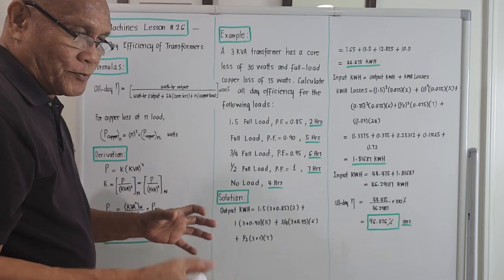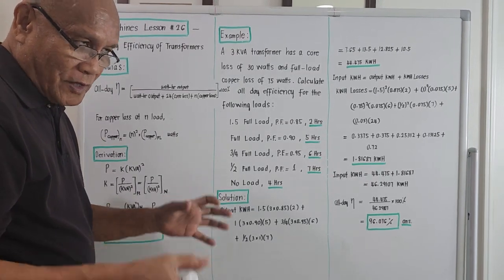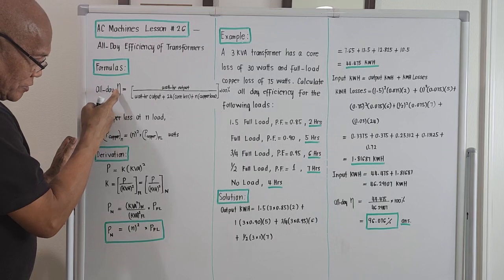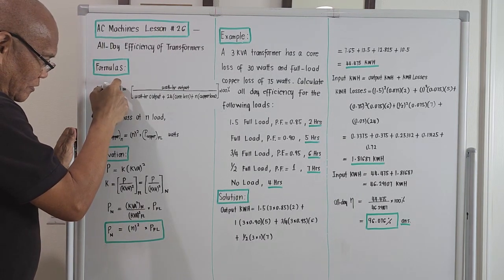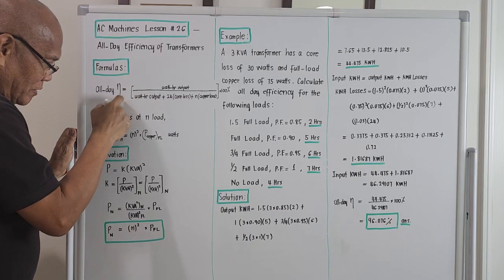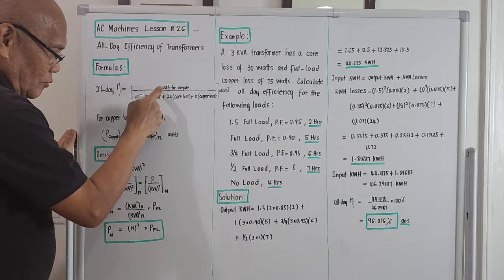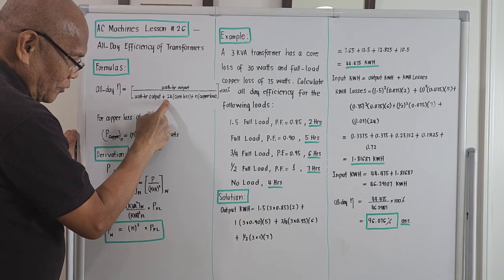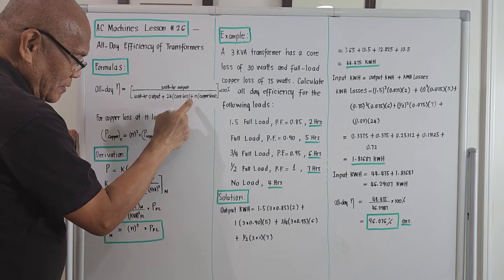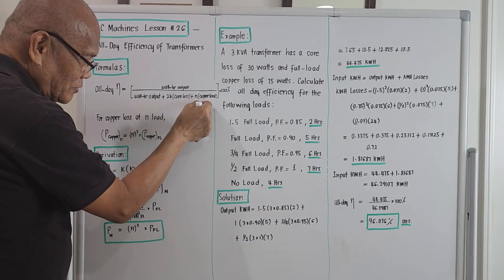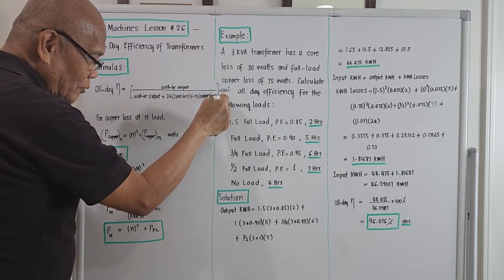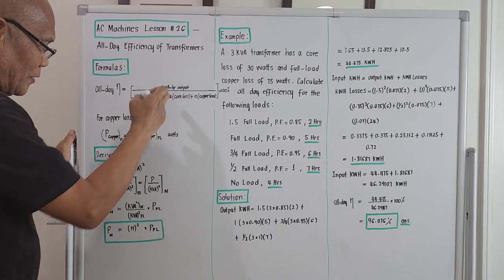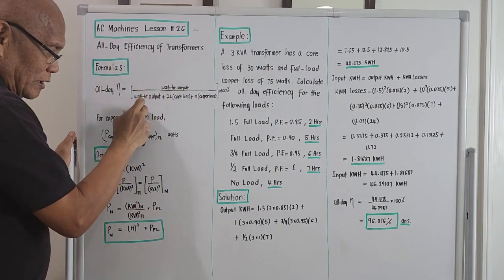Let's bring out the formula for computing the all-day efficiency of a transformer. The symbol for efficiency — it looks like a Greek letter with a tail — equals watt-hour output over watt-hour output plus 24 times the core losses plus n times the copper losses, all times 100 percent. Simply put, it's watt-hour output over watt-hour output plus total losses.